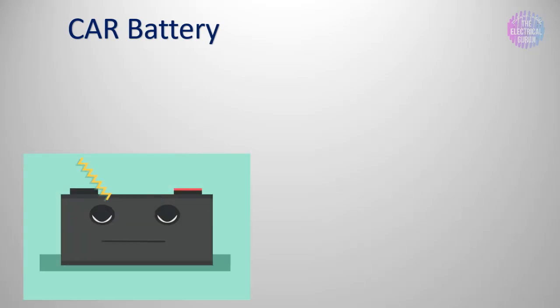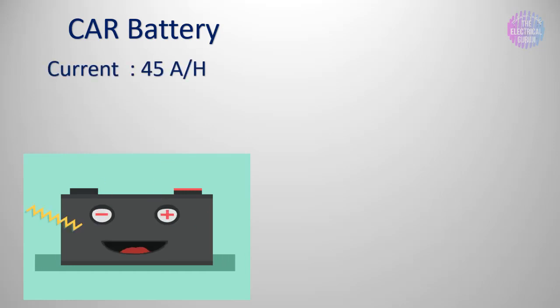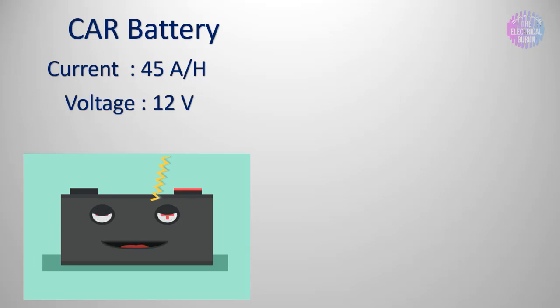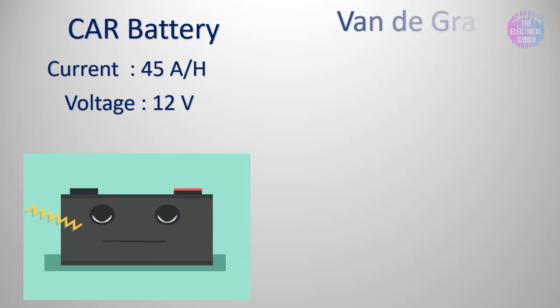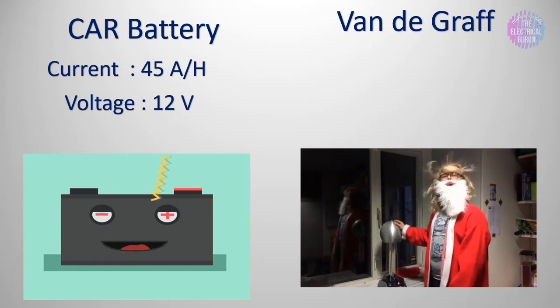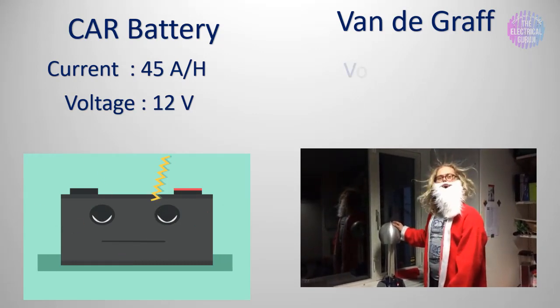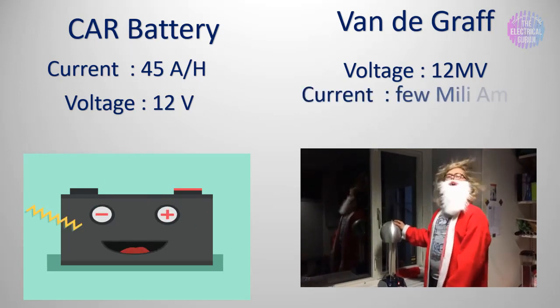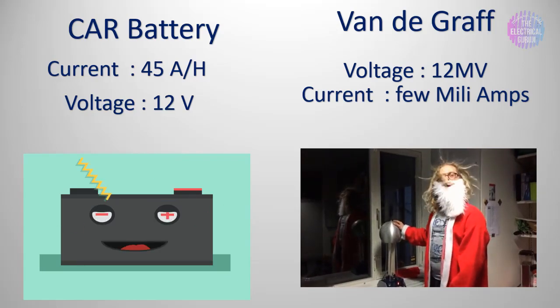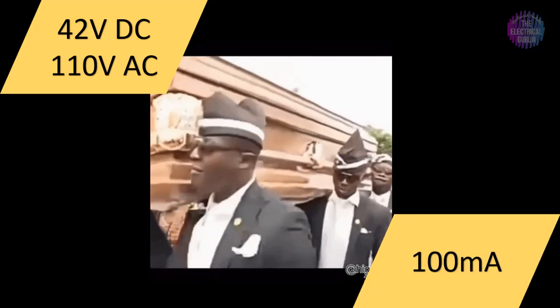Consider two contradictory examples. A car battery has 45 amperes but doesn't cause a shock because it has only 12 volts, and 12 volts is not sufficient to force that current through a body with 100,000 ohms resistance. On the other side, a Van de Graaff generator produces voltage of around 12 megavolts, and still we don't get severe shock because it produces only a few milliamperes of current. Hence, when voltage is above 42V DC or 110V AC and current is above 10 milliamperes, we get a shock, and if current goes beyond 100 milliamperes, it's lethal.